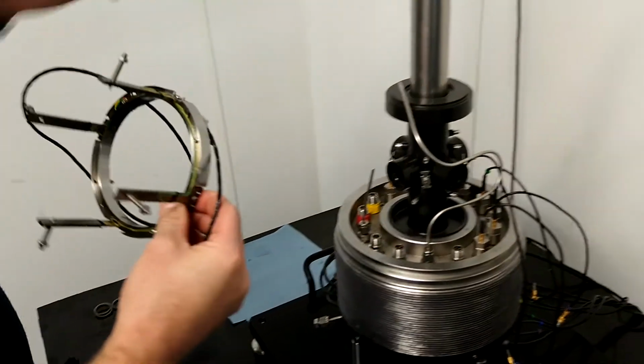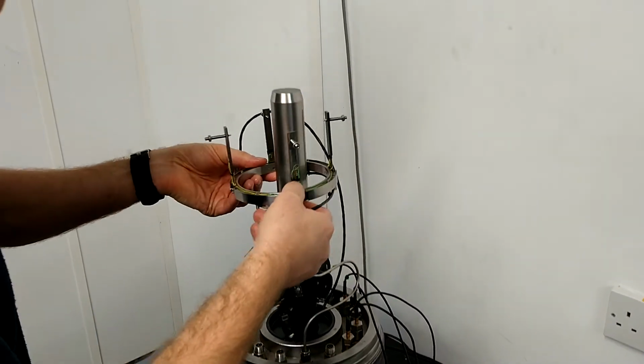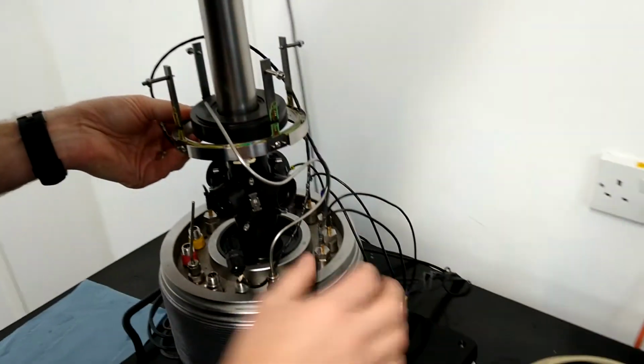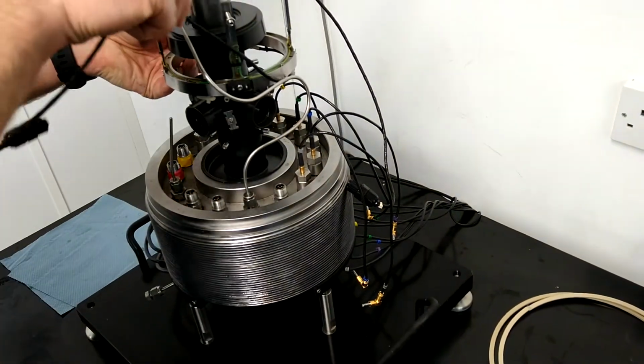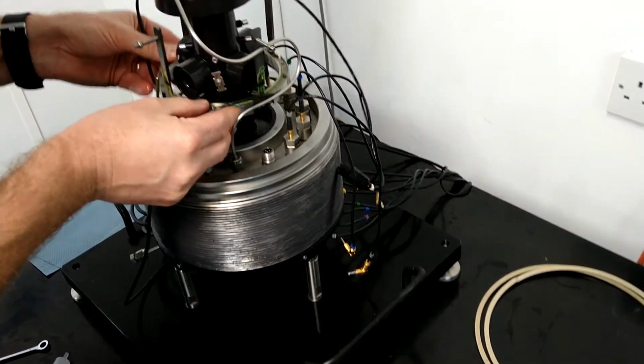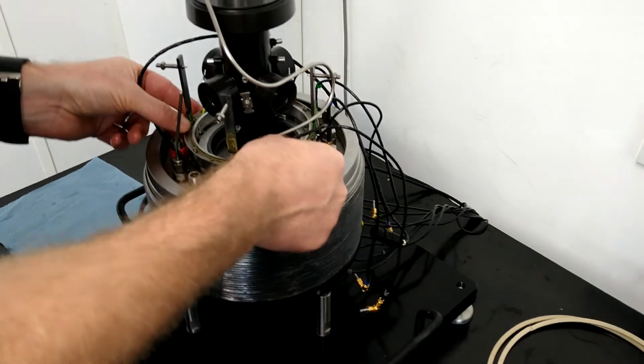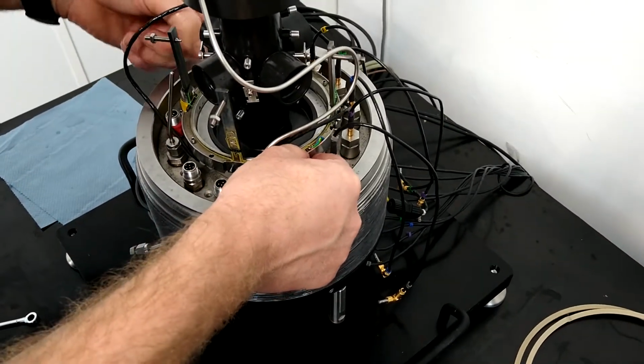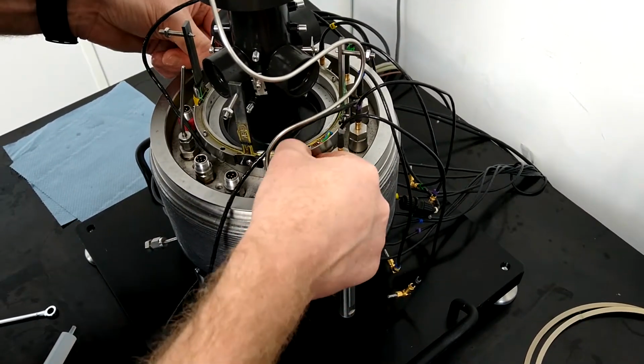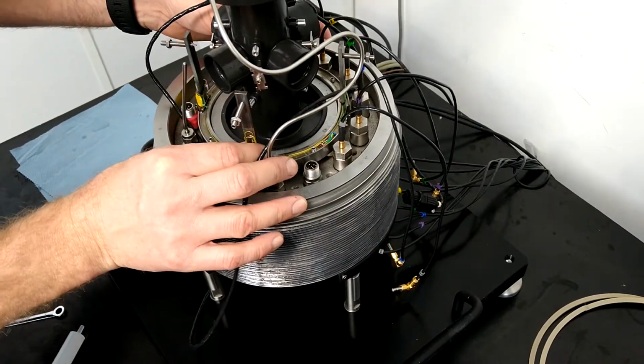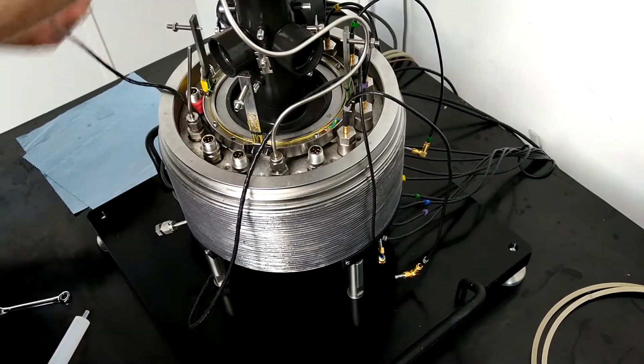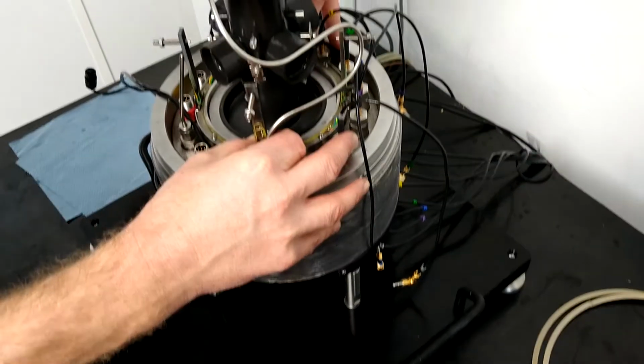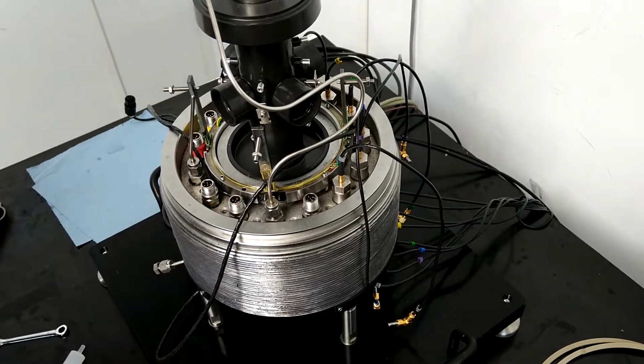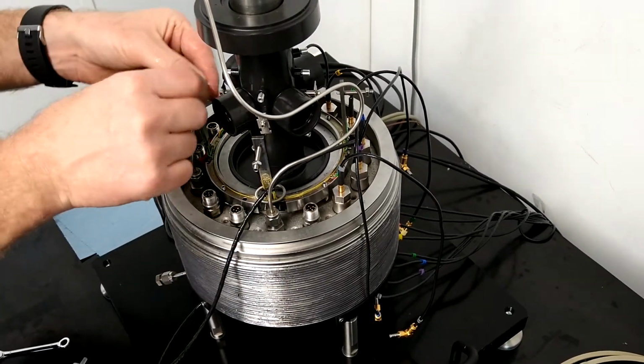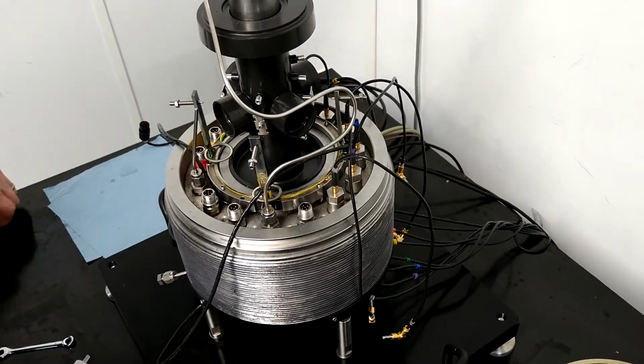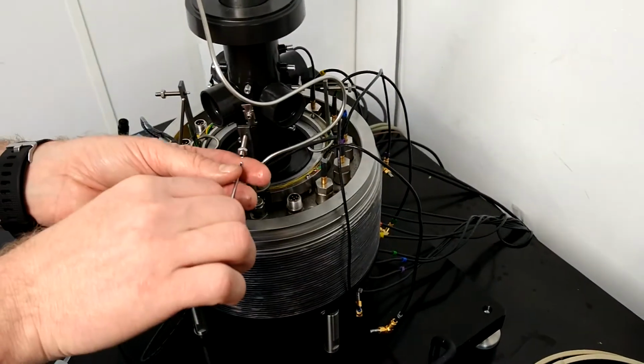Wind the feet on the radial caliper out until flush on the upper side. Place the radial caliper over the membrane, aligning with the caliper inserts. Place one spring over each measurement arm before winding the connection pins so they are almost touching the caliper inserts. Readjust the feet for better alignment if required.